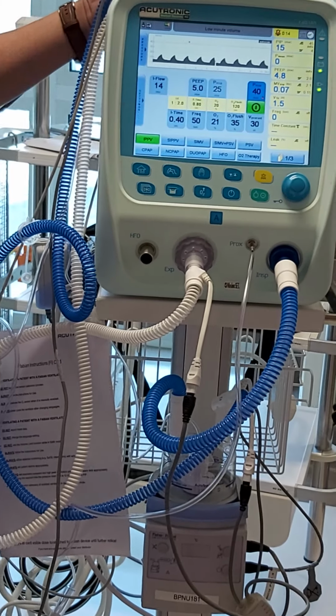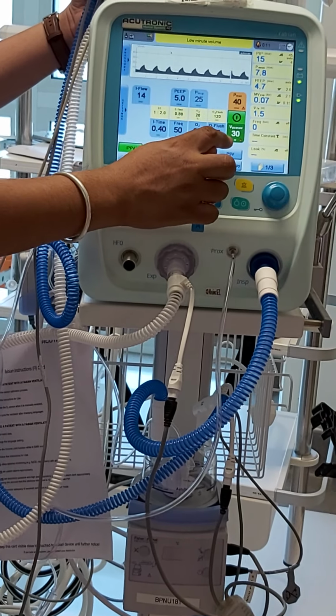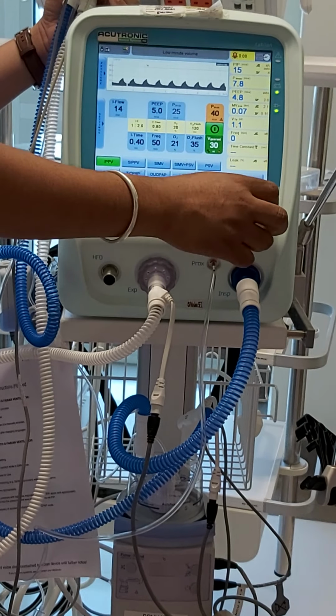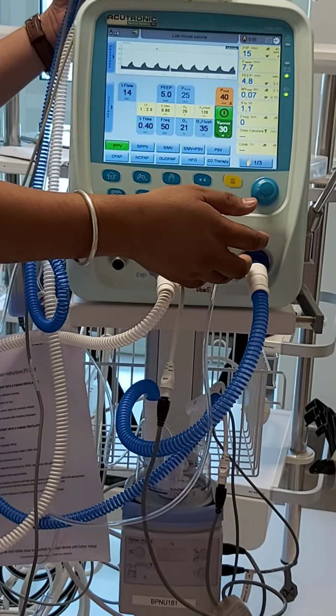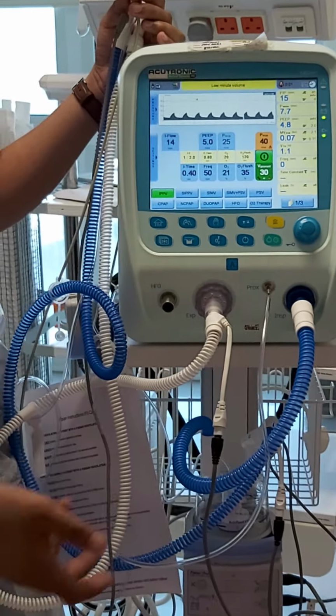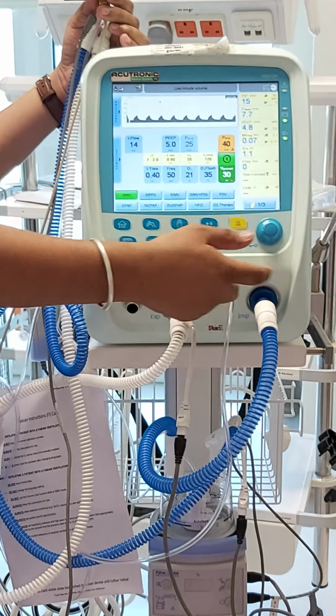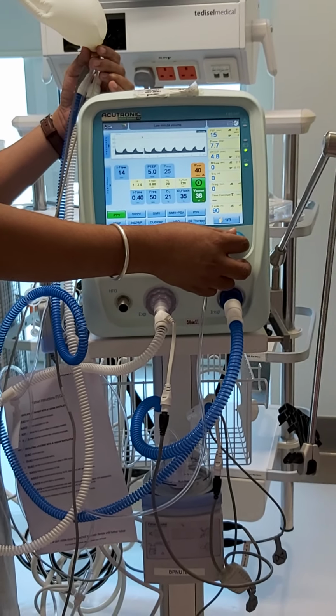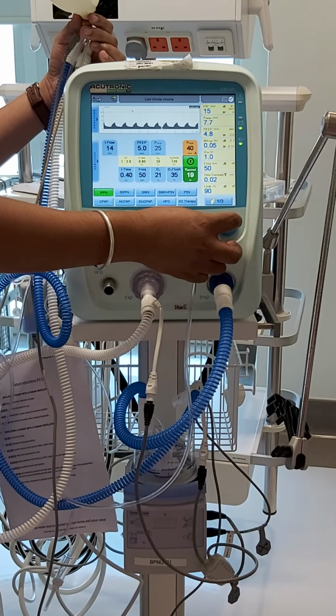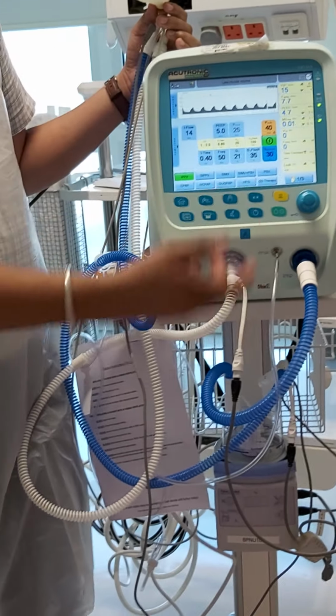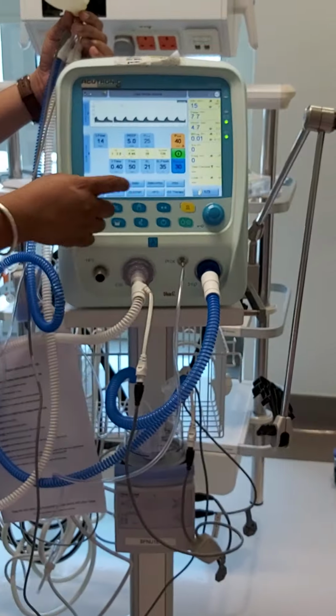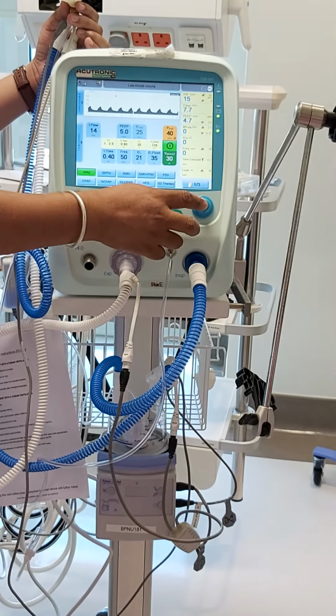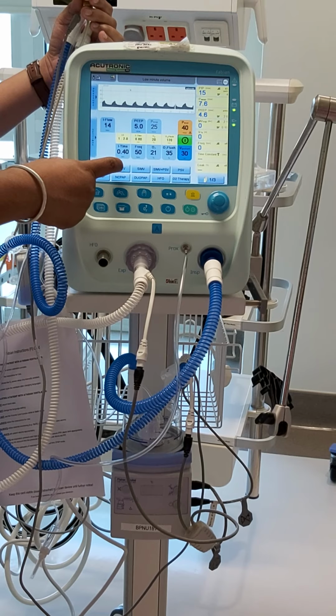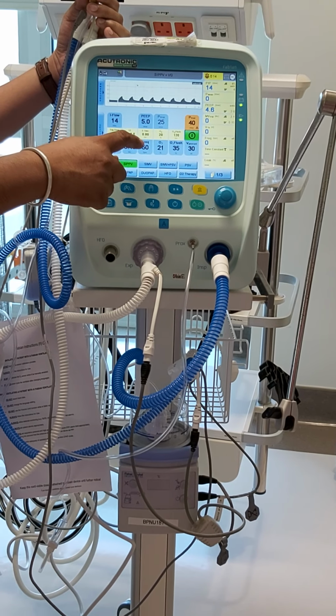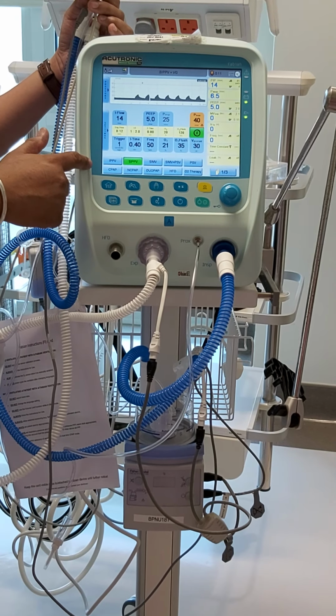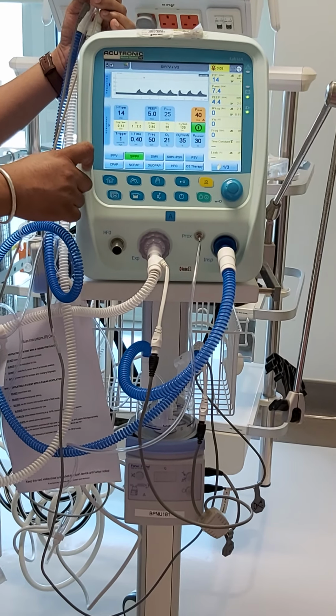Get 40. Ma'am, you notice what happened is, if I reach 30, there's an automatic lock. The machine will not allow you to go beyond 30 like that. But if the doctor wants more, you can press this to unlock, and then you can change it. This is the same for all the other parameters which have an automatic lock. If you have an automatic lock, you have to unlock that. Whenever you change something, for example I go to SIPPV, you notice that the frequency is not changed, because it is the same as what you set in IPPV. There are other things which are different.